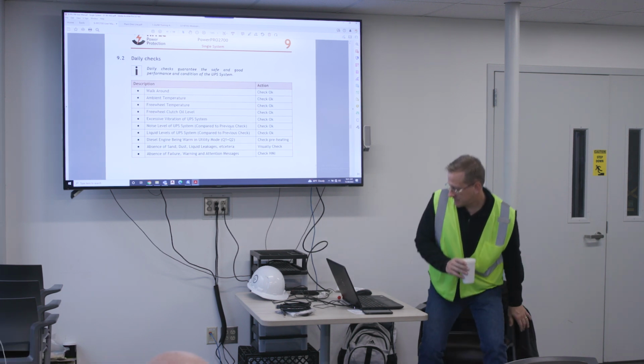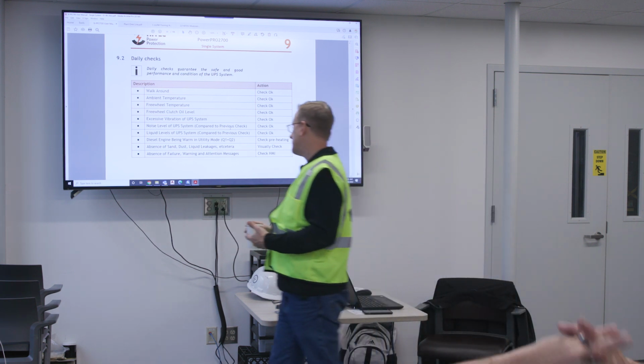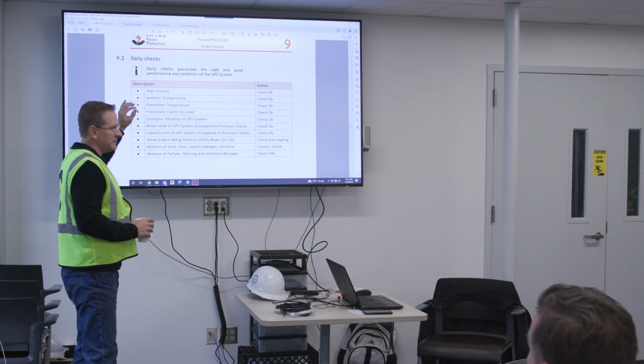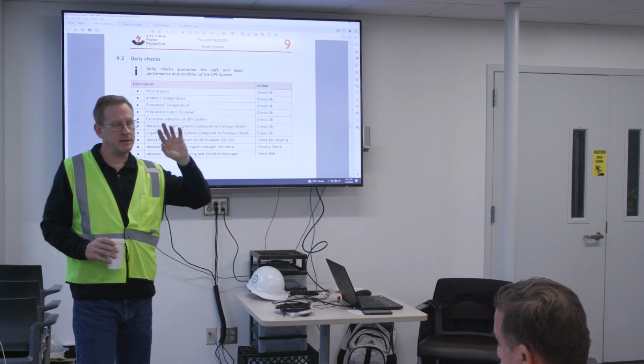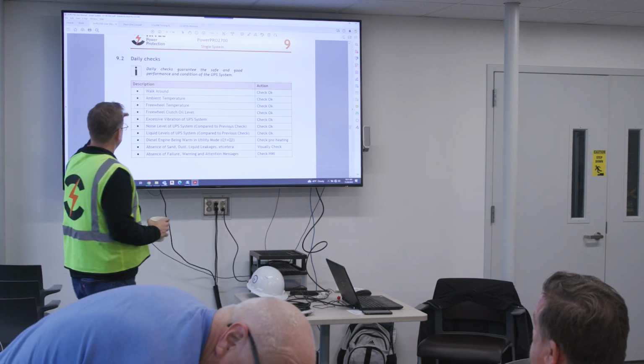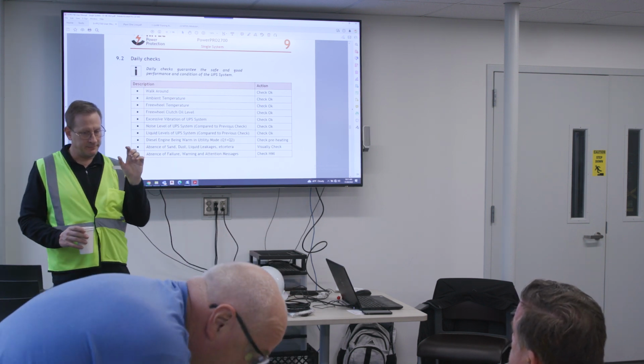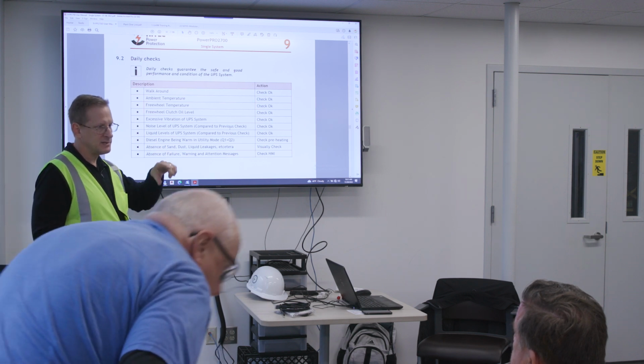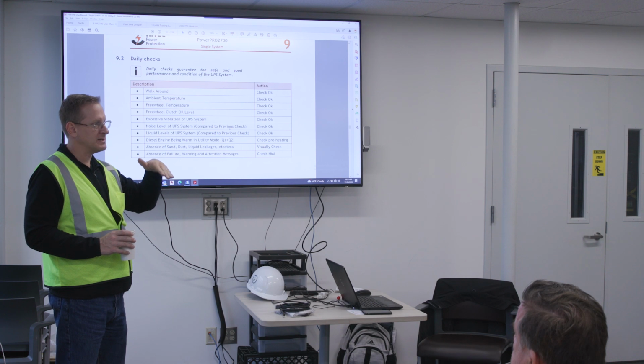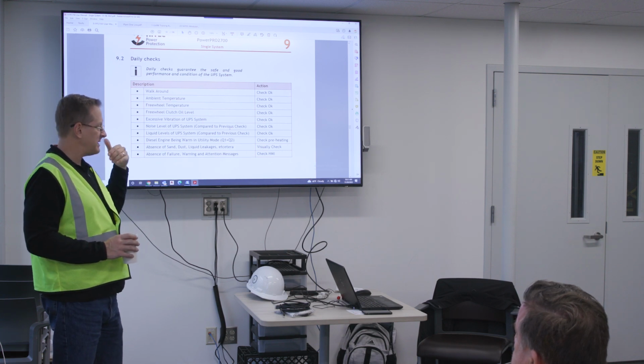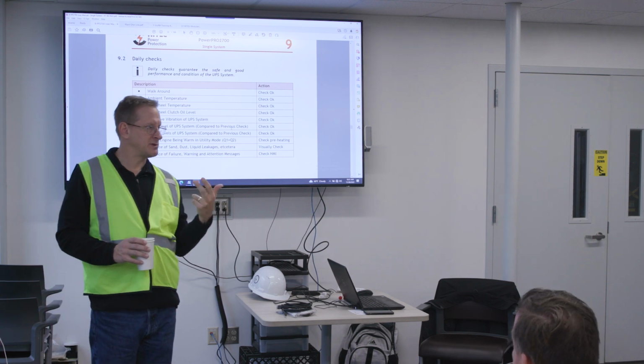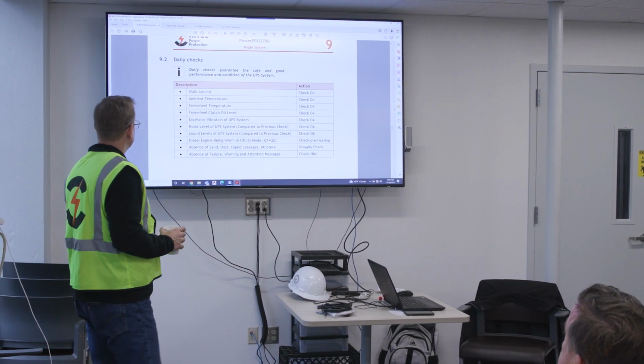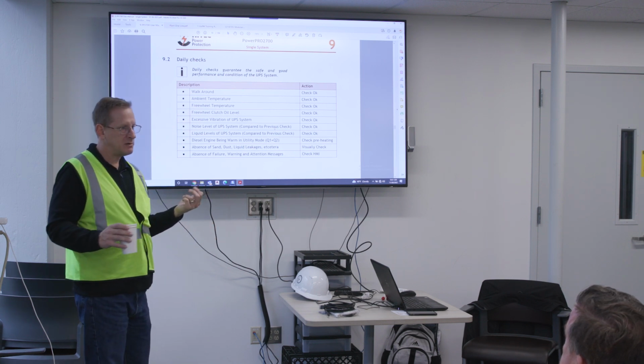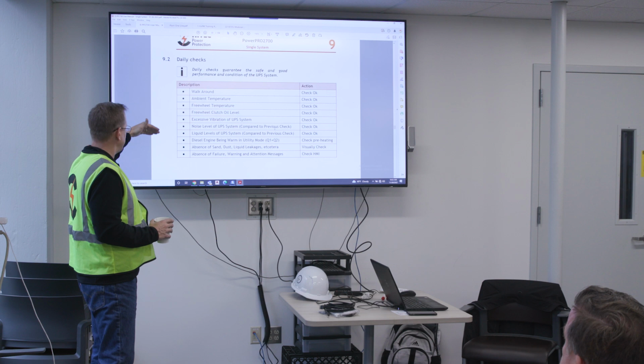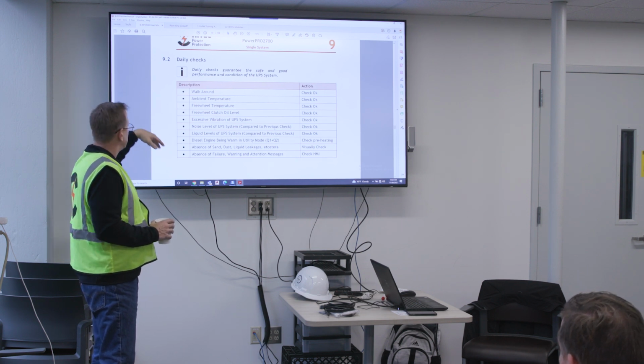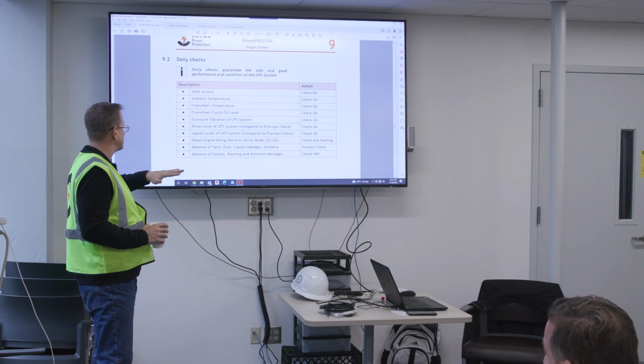As far as daily checks, they're not too involved and don't take a lot of time. We're talking about walking around the unit, listening, watching, feeling, looking at temperatures. There are sight glasses on the clutch - make sure the oil level is where it needs to be. The HMI has information you can check to make sure your temperatures are good, and SCADA has temperatures on it too, so take a glance at that. Basically, you're just looking at temperatures, oil levels, water levels, making sure everything is where it's supposed to be.